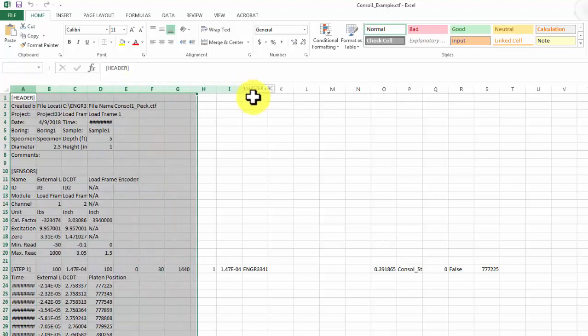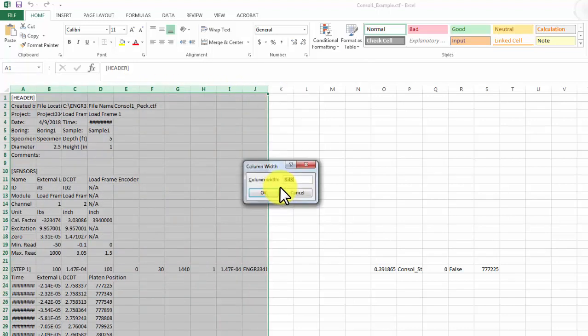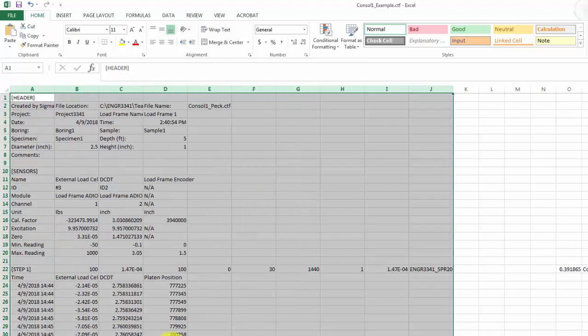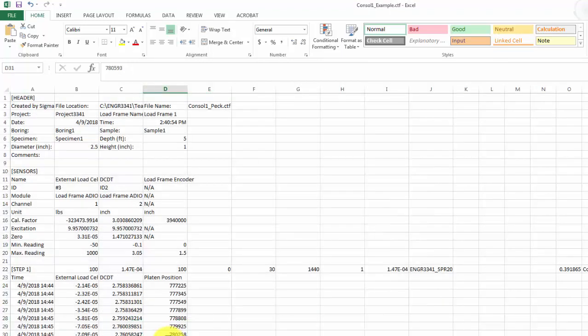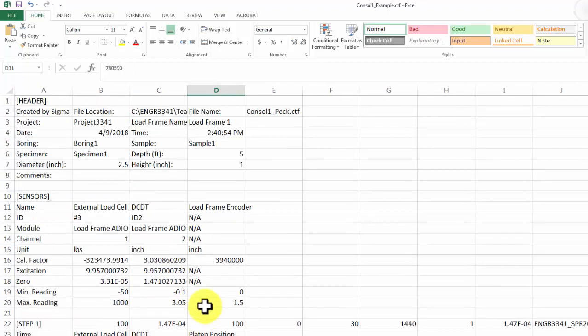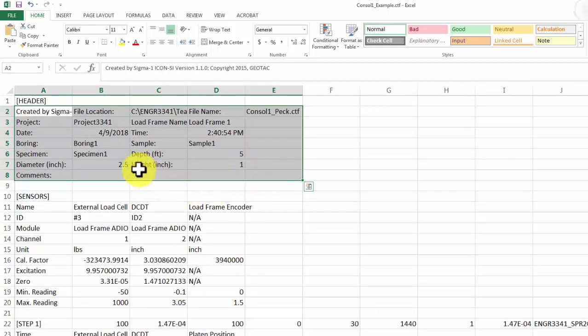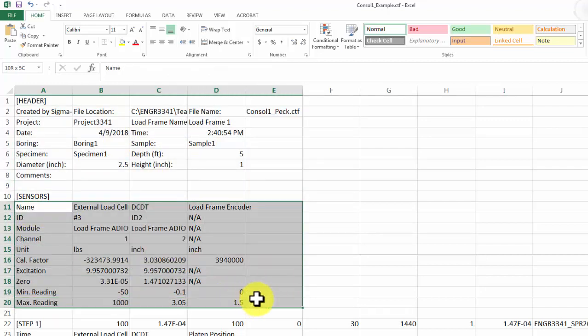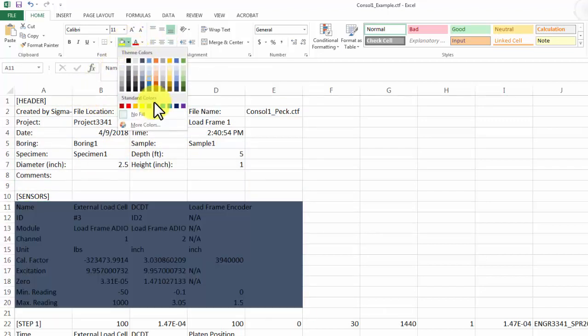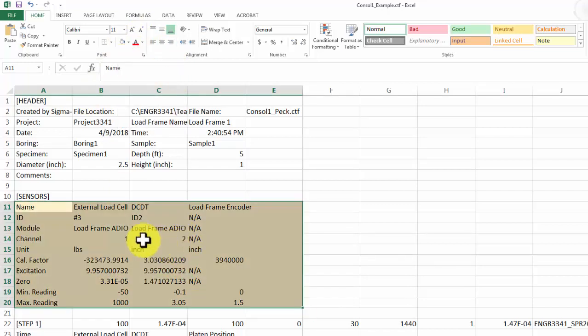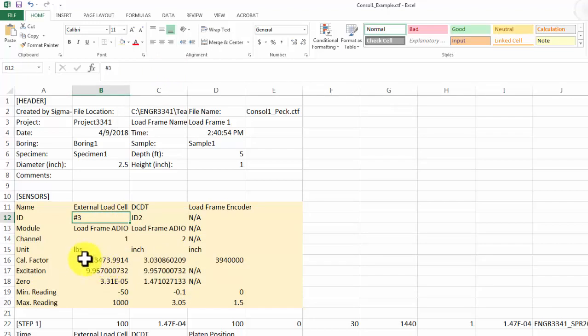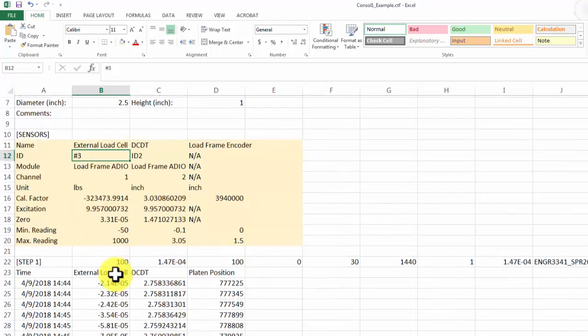You'll have to expand the columns — I find that setting a column width of about 15 works well. Once you've done that, you'll find that the data file is divided into three sections. The header section at the top has basic information for your file: where it was stored, the project number, the sample descriptions, and that information. The second section has all the data for the sensors, highlighted in yellow, including calibration factors, excitation voltage, and other information we'll need.